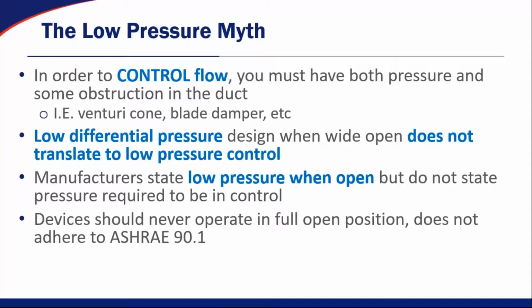But the problem with that is the low differential pressure design when wide open does not translate to low pressure control. So if you try to control pressure with a given accuracy at those low differential pressures, most of the time the competitors that are claiming these ASHRAE 130 low pressure drops have an accuracy range of about plus or minus 15%, because just like those flow measurement characteristics that have a low accuracy with a high turndown ratio because of that transducer, you still need a minimum velocity and minimum pressure to be able to control to an accuracy level comparable to what Phoenix Controls has.